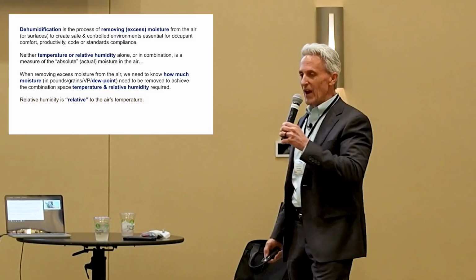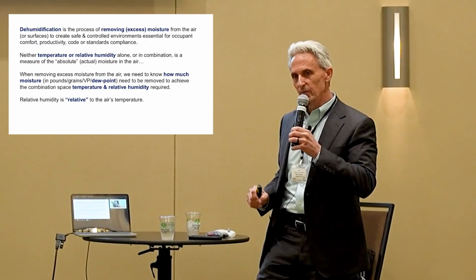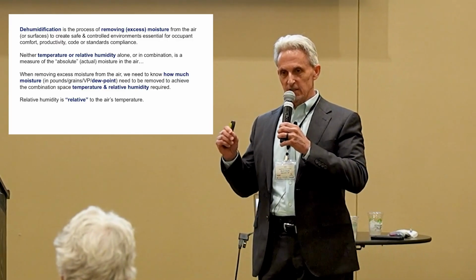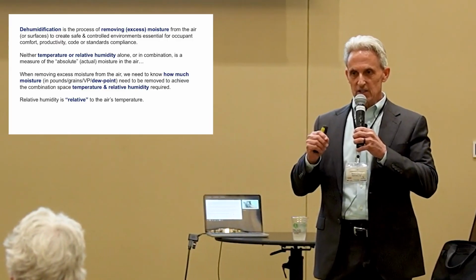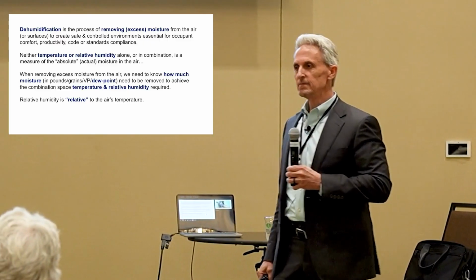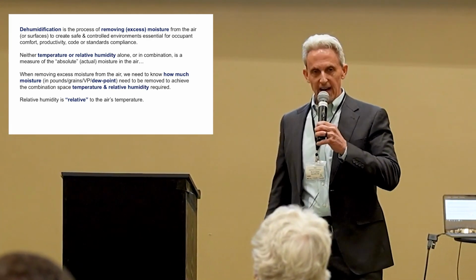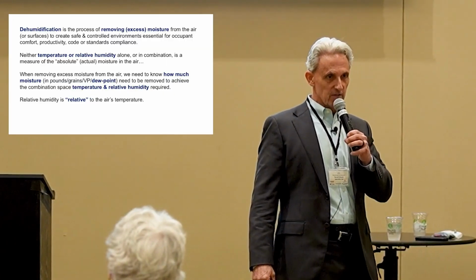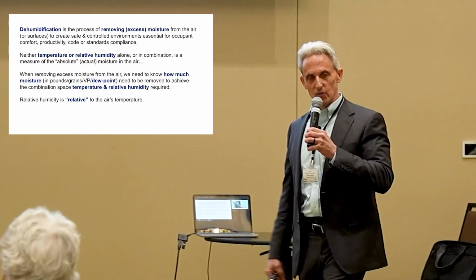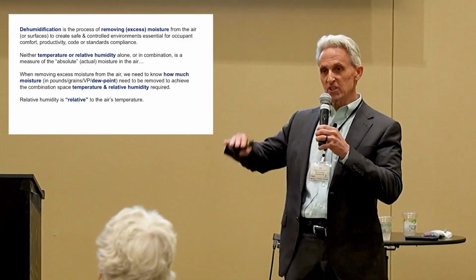Relative humidity is relative to the air's temperature. In itself, it means nothing. Let me ask you right now, in a room at 75 degrees Fahrenheit and 50% relative humidity, or in a room at 80 degrees Fahrenheit and 40% relative humidity, which room has more moisture in the air? 75 degrees and 50% relative humidity, or 80 degrees Fahrenheit and 40% relative humidity. If I'm gauging it on relative humidity alone, I would assume the 80-degree room would have less moisture in it. It has more. It has more absolute moisture in the air.